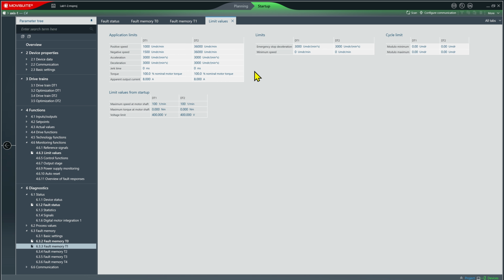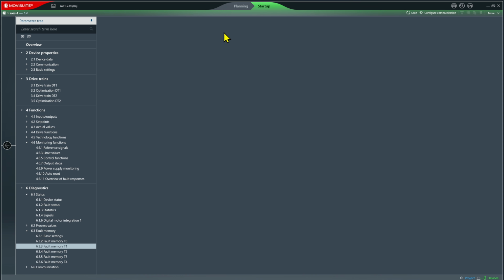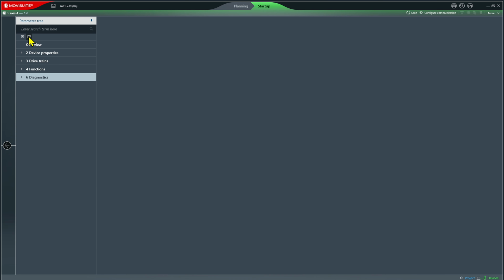But we're going to go through that process anyway, because normally that's a really smart thing to do when you do a commissioning. So I double click on the top of the VFD circle. And notice everything is still open from my last lab activity, so let's clean up our screen a bit. I'm going to right-click on one of these tabs and close all the tabs. I'm also going to collapse all my menus, and now go to the Device Properties menu, expand it, and then expand the Basic Settings submenu, and open Reset Device Parameters.